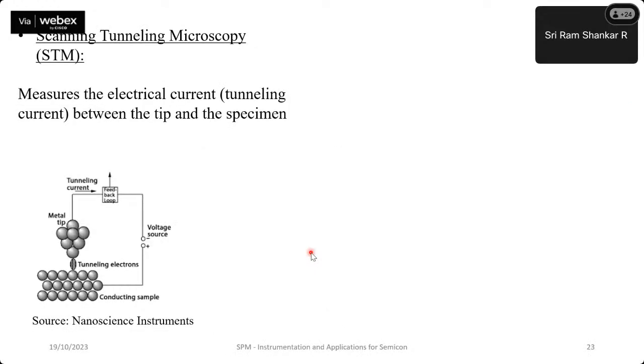For example, in case of scanning tunneling microscope, we measure the tunneling current between the tip and the sample. You apply a certain bias between the tip and the sample, and when the electron clouds are closely interacting with each other, a tunneling current will be set up, and that current depends on the distance of separation between the tip and the sample.